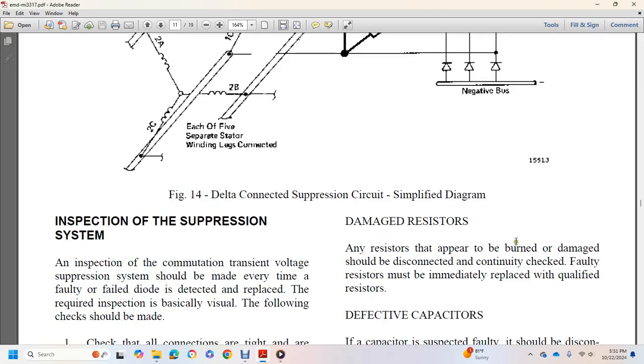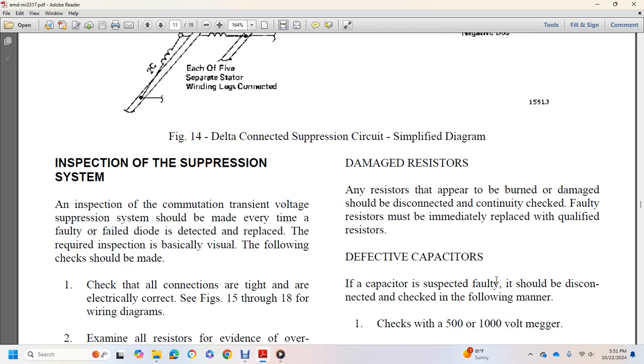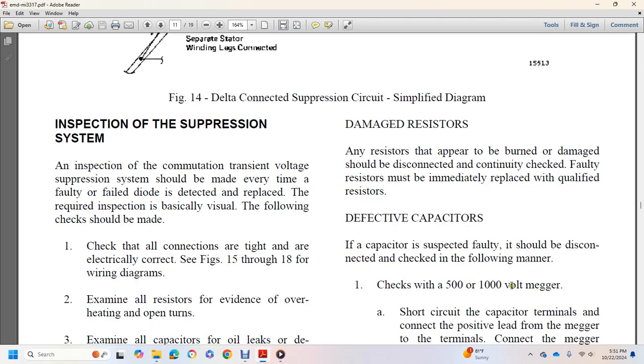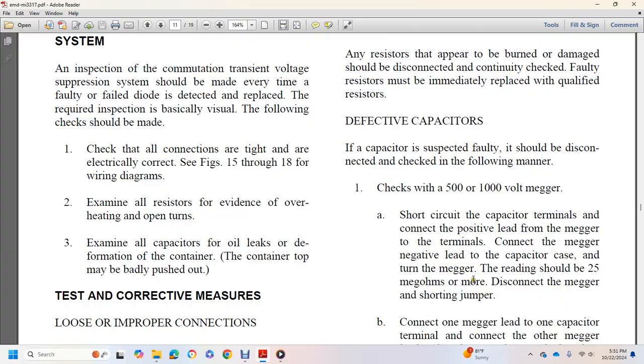Damaged resistors. Any resistor that appears to be burned or damaged should be disconnected and continuity checked, and faulty resistors must be immediately replaced with qualified resistors. Defective capacitor: a capacitor suspected faulty should be disconnected and checked in the following manner. Check with a megger between 500 and 1000 volts. Short circuit the capacitor terminals, connect the positive lead of the megger to the terminal and the negative lead to the capacitor case.